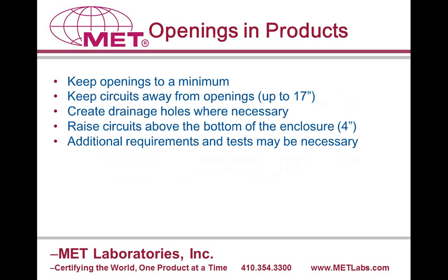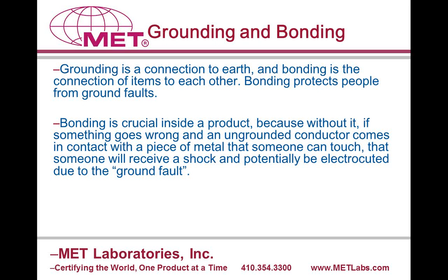One way to handle the heat that's generated in a piece of equipment is to provide ventilation openings. However, you need to keep these to a minimum and keep them small. The bigger they are, the further distance the live parts need to be away from them. For example, if you have a small 3/4 inch opening, then your live wires have to be at least 4 inches away. If you have a large 2.5-inch opening, your live wires have to be at least 17 inches away. Again, it's very important that you keep your ventilation holes small.